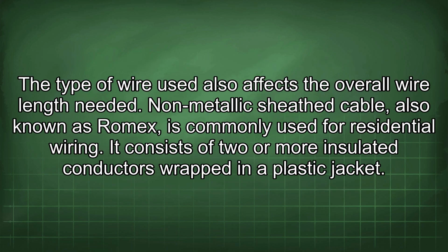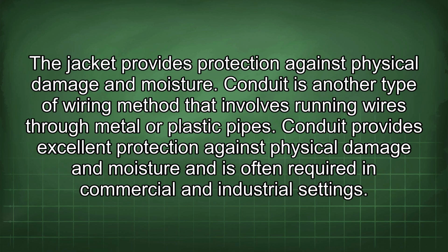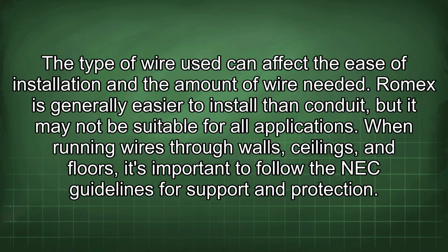The type of wire used also affects the overall wire length needed. Non-metallic sheath cable, also known as Romex, is commonly used for residential wiring. It consists of 2 or more insulated conductors wrapped in a plastic jacket. The jacket provides protection against physical damage and moisture. Conduit is another type of wiring method that involves running wires through metal or plastic pipes. Conduit provides excellent protection against physical damage and moisture and is often required in commercial and industrial settings. The type of wire used can affect the ease of installation and the amount of wire needed. Romex is generally easier to install than conduit, but it may not be suitable for all applications.